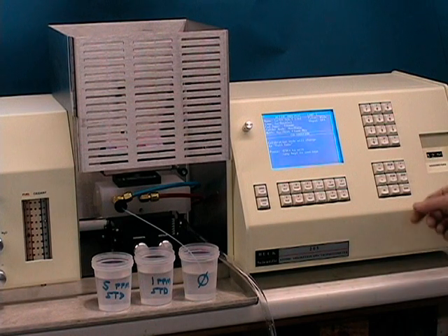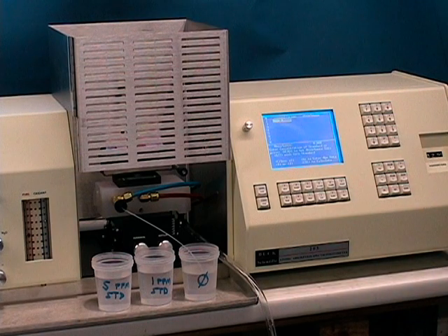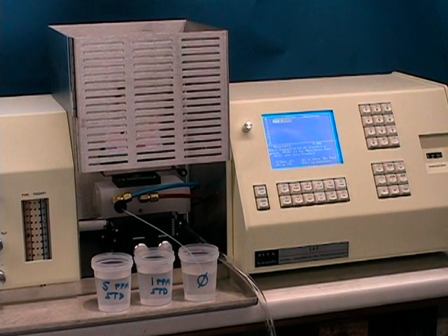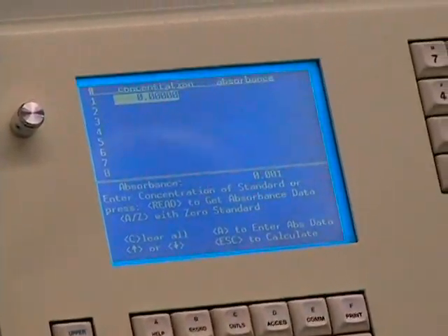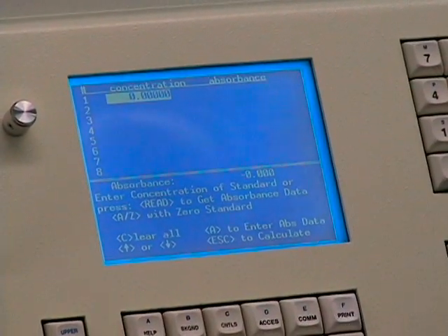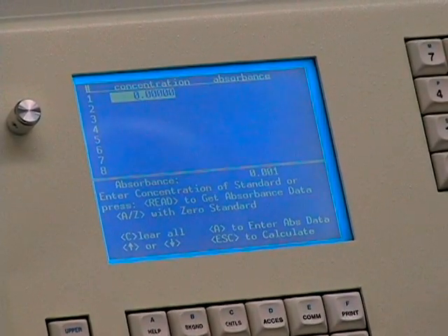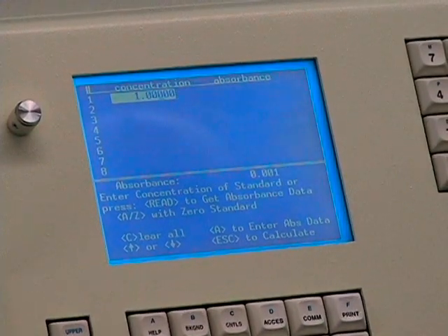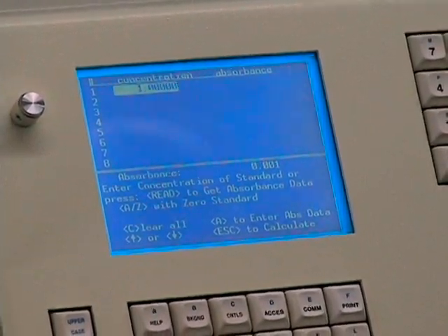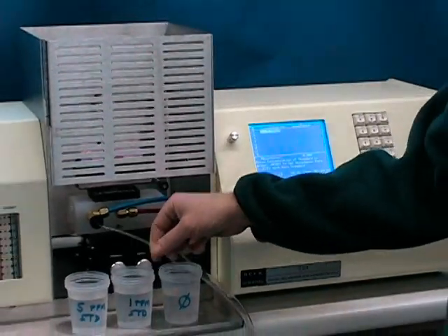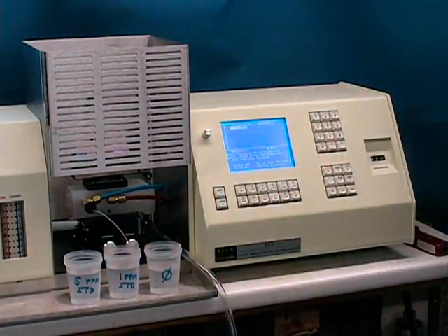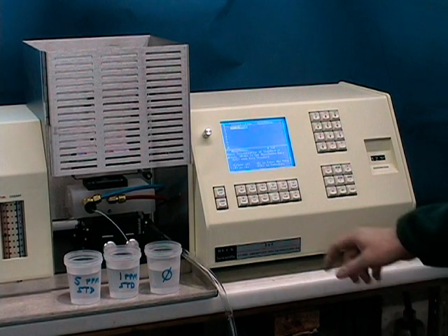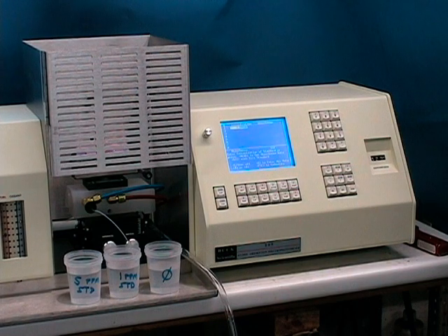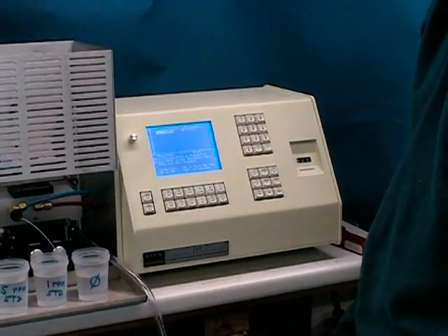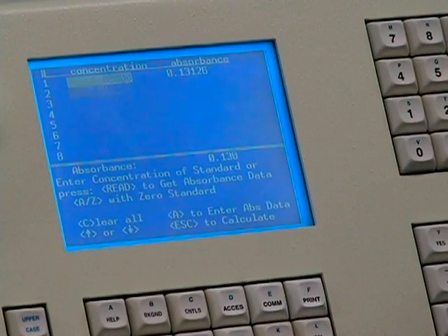Press enter to enter the concentration mode as opposed to the absorbance mode, and you will see the first line highlighted. The 205 uses a fixed decimal point notation, so using the cursor arrows, scroll over to the decimal point and enter in your first standard, in this case 1.0, and press enter. Then aspirate your 1 ppm standard. Wait a few seconds for it to equilibrate and press the read key. This will take a several second integration, and put the value in the absorbance column of your calibration table. Scroll down to the next line.